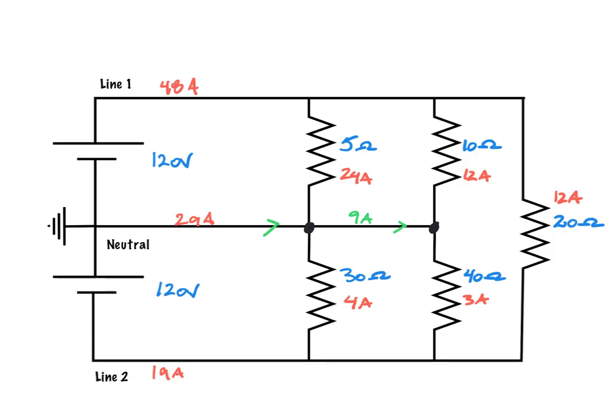Everything remains in balance. So it's all about understanding your nodes and the fact that whatever enters a node has to add up to the other side. So again, 4 amps came to this point, became 24, so therefore it picked up 20 amps, which left it with 9 left over from this 29. That traveled along, added to the 3, and then ended up giving us the 12 amps on the top. So it's almost fun to work these things out, and that is how we calculate all the currents on the neutrals in an unbalanced 3-wire circuit.